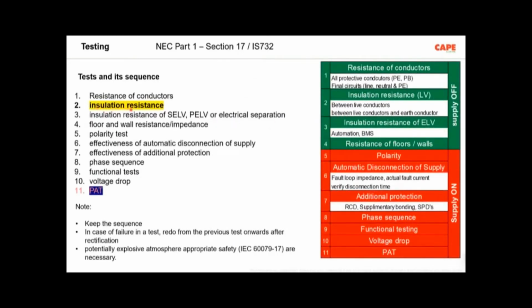One is test number 2, insulation resistance. The minimum insulation resistance between a current carrying conductor and the earth must be higher than 1 mega ohm. If the resistance is less than 1 mega ohm, you are supposed to rectify the problem immediately. Now, I have also included a test number 11. Tests 1 to 10 ensure that your electrical installation, the wiring and the protective devices, are operating in very good condition. But tomorrow, if portable devices are plugged into your good electrical installation, and you have a portable device which is faulty, of course, fire can happen.